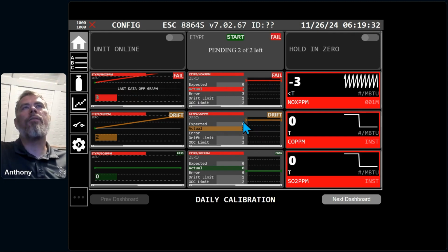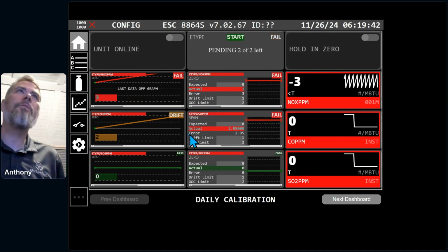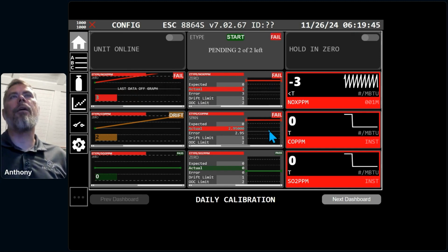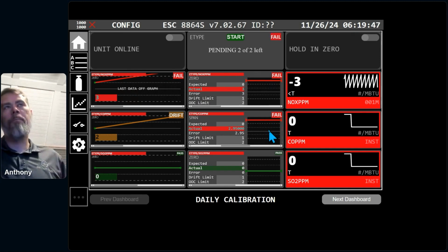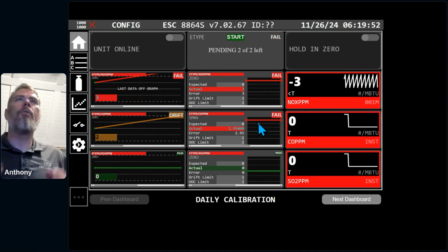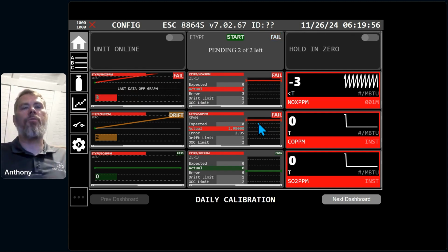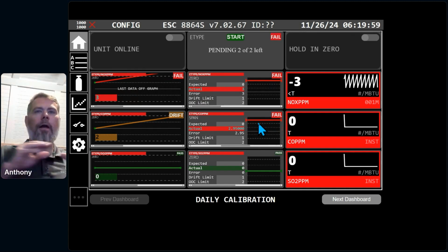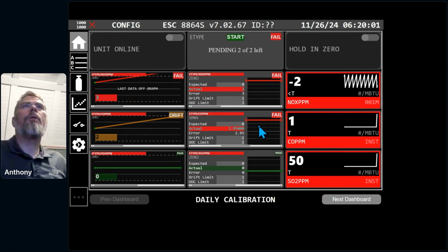And so you can see in this particular phase, we were right on the OOC line, where it's overlapping it actually. But if we look at the next one, we can see there's our OOC line, and we failed. The biggest difference between the trend graph and the detail graph, other than it only shows one data point, is that the detail graph, this one here, will scale as large as it needs to show all the actual results. It won't show a line off the graph. And so again, you'll see your OOC limit and your maintenance line with your reference here in the middle.